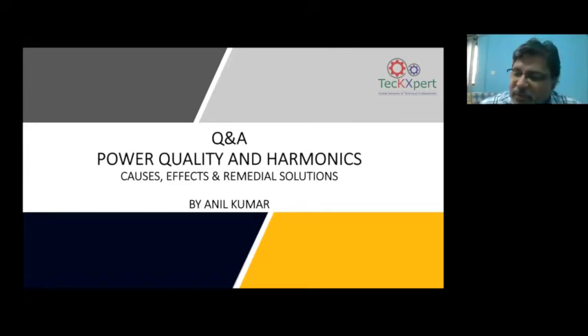Okay, sir. These line reactors at the VFD drive input, will they affect the DG operation when the power changes over from EB to generator? Will it affect the voltage regulator because of this? This line reactor will not have any impact on that, because the line reactor is just sitting there to reduce the harmonics coming out of the VFD. In one way, it is good that the generator will not get subjected to that level of harmonics coming from a drive. So I would rather say a line reactor is a good solution, and it is rather helpful for the generator.